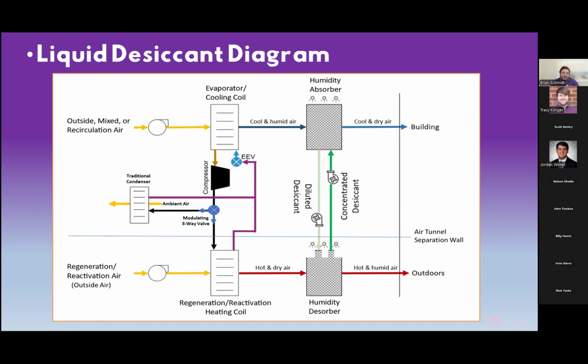So underneath the absorber is a plastic tray, underneath the desorber is a plastic tray. If anything catastrophic were to ever happen, it's PVC piping. Let's just say a maintenance person goes in and accidentally trips, breaks one of the PVC pipes. That liquid desiccant would then flow into that plastic tray where we have leak detection systems. If those leak detection systems are tripped, it will turn off the liquid desiccant system. So it will stop those pumps.